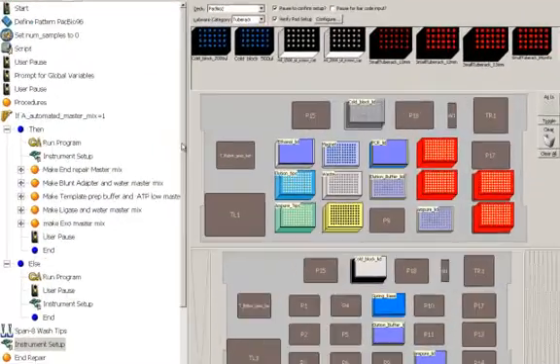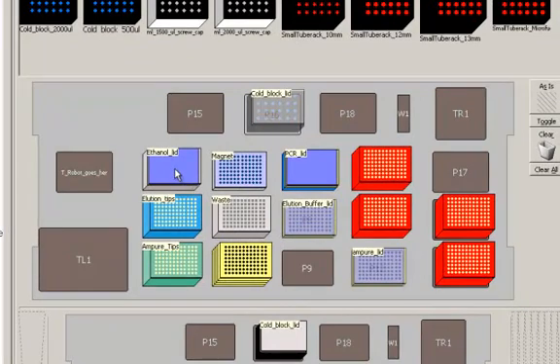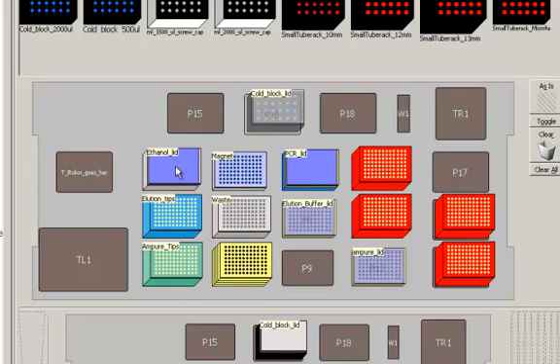Now let's look at the instrument setup. We have ethanol here or an ethanol lid that sits on top of a 96 well deep square plate that stores our ethanol for the Ampure washes. It's a 96 well deep square. You'll only need to put ethanol in the wells that correspond to the pattern where you have samples. We have elution tips and Ampure tips. These tips are used for every Ampure step in the process. They are not washed between Ampure steps.